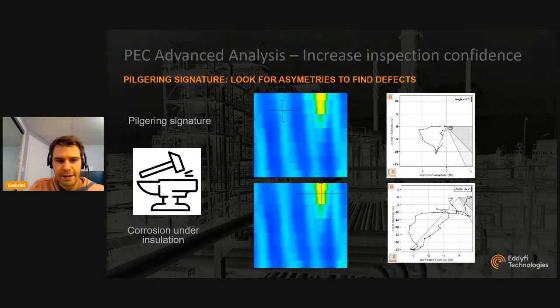Pilger signature, that helix pattern that you see here on the pipe, is not so common in the field, especially in refineries, because the pipes are thermally and mechanically cycled over time, and that does a kind of healing process on the pipes. That takes off the cold work marks or localized changes in magnetic properties that were induced during the manufacturing process of the pipe that can affect the PEC signal. So you see that more often on pipes that are not very hot or not under high pressure or quite new, especially in manufactured samples. So the tool is not able to differentiate that from a defect.